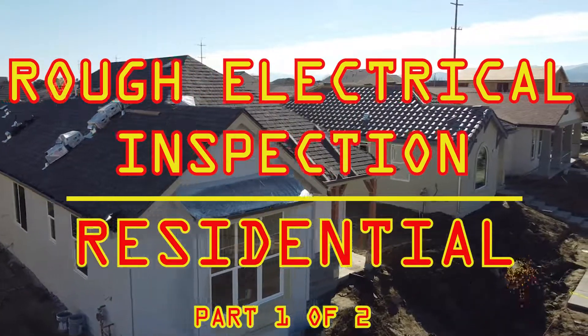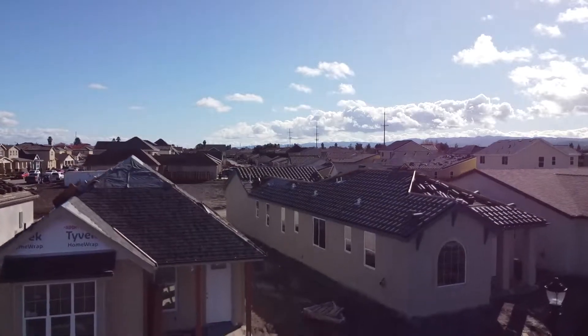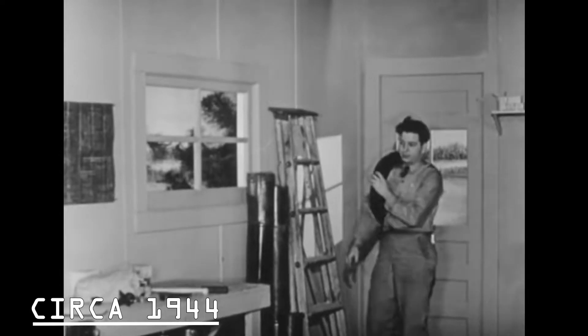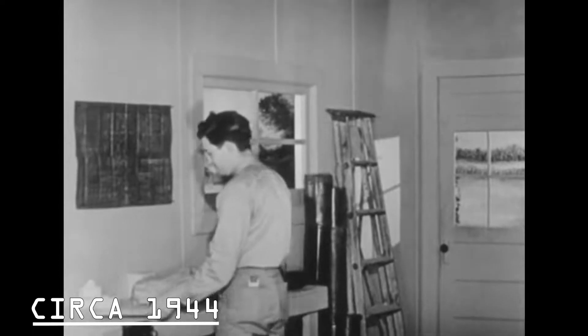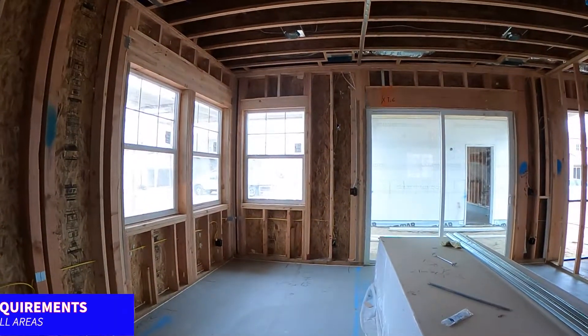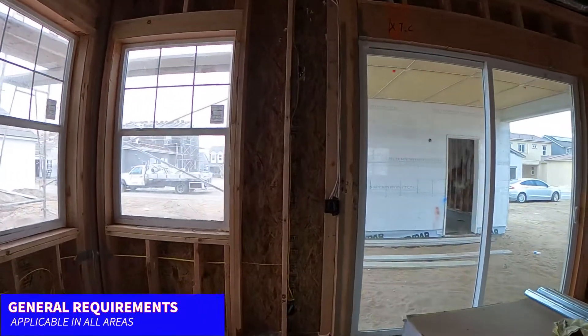This video will present a basic rough electrical inspection in a new single family dwelling. The electrical cable shown in this video will be non-metallic sheathed cable, which is the most widely used wiring method in residential construction. Non-metallic sheathed cable wiring shall comply with the provisions of articles 300 and 334 of the National Electrical Code. Plan the work thoroughly and consult your local inspector for local regulations. I will now start by going over general requirements which apply to all the rough electrical work, regardless of the area installed.